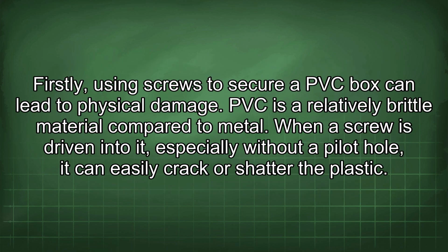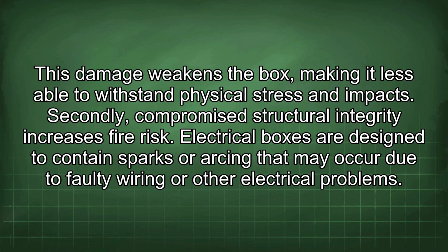Firstly, using screws to secure a PVC box can lead to physical damage. PVC is a relatively brittle material compared to metal. When a screw is driven into it, especially without a pilot hole, it can easily crack or shatter the plastic. This damage weakens the box, making it less able to withstand physical stress and impacts.